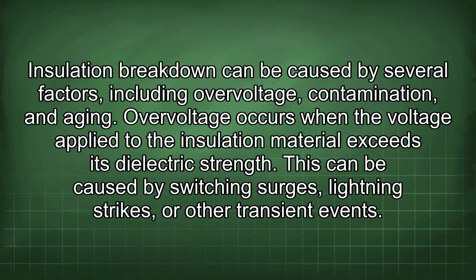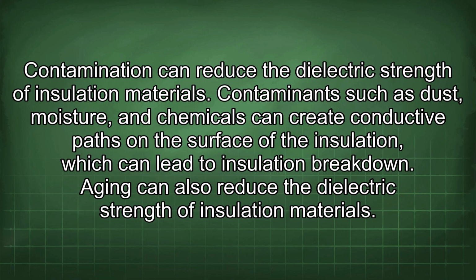Overvoltage occurs when the voltage applied to the insulation material exceeds its dielectric strength. This can be caused by switching surges, lightning strikes, or other transient events. Contamination can reduce the dielectric strength of insulation materials. Contaminants such as dust, moisture, and chemicals can create conductive paths on the surface of the insulation, which can lead to insulation breakdown. Aging can also reduce the dielectric strength of insulation materials.